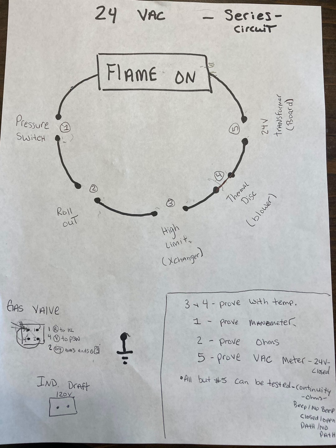Once it finally closes that path, we want to take a temp probe. We like the K-type temp probes that plug into our meters, and we can install a temp probe right in behind that high limit switch, screw the high limit back in, run sequence. If that high limit switch trips again, we're going to be able to see exactly at what temperature that happened, and you can prove a switch very fast.